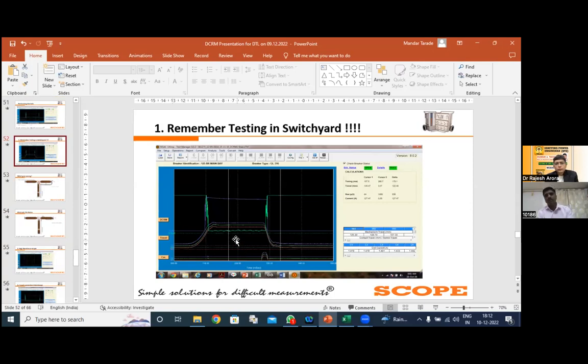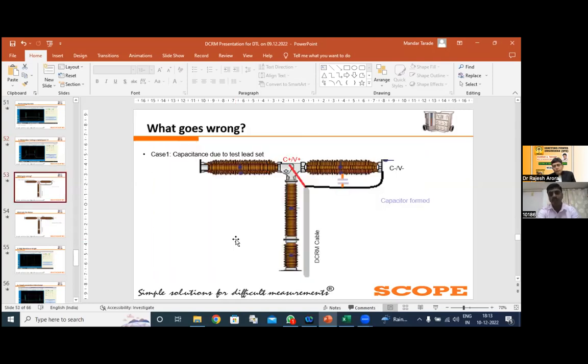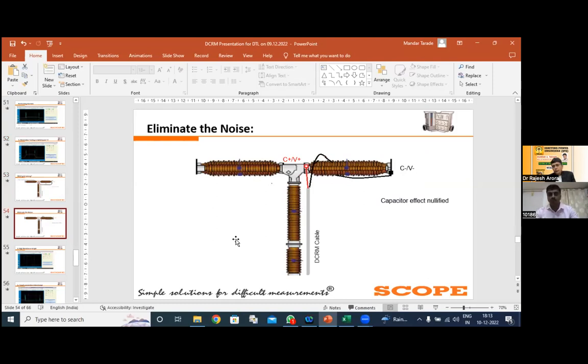Because whenever, after successful closure of your CB, you are issuing the trip command from time instance 0 to 300 millisecond, after auxiliary changeover we are removing the positive supply of your coil. And once your mechanism is completely stabilized, we are not expecting any change in the behavior of your static contacts. But still, in spite of that, if you are getting behavioral changes, that is because of the noise coupling, that is because of the external conditional noise. Maybe it is a low frequency noise or a high frequency noise. If it is a low frequency noise, then you need to take one wrap. This is the first thing. If it is a high frequency noise, then you need to cross check. Either you can earth the breaker from both sides, or you can remove one earth. Accordingly, you can eliminate the high frequency noise also.